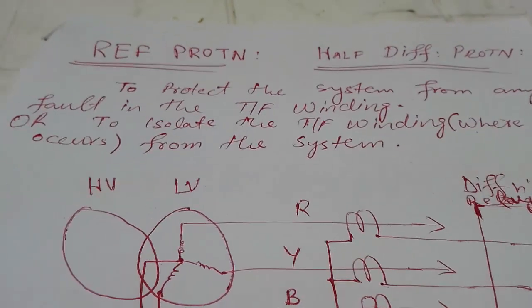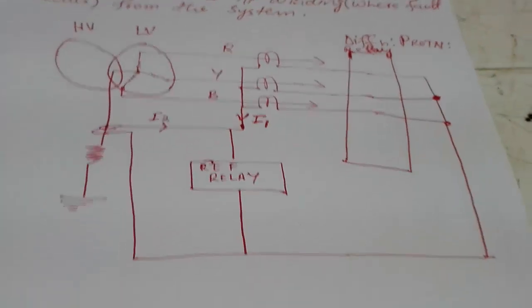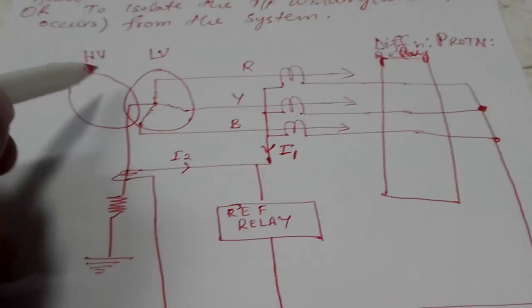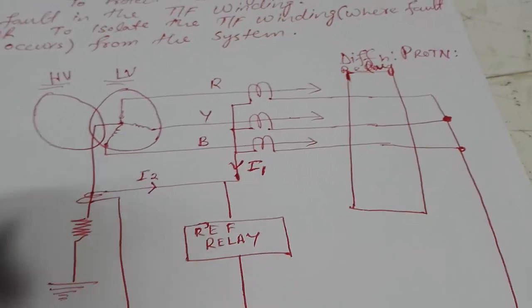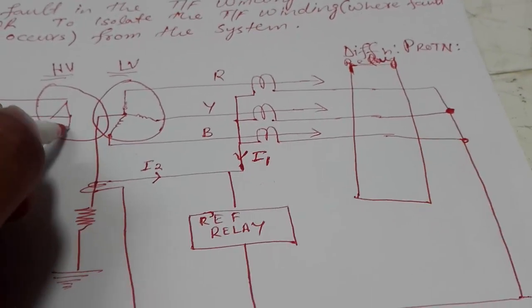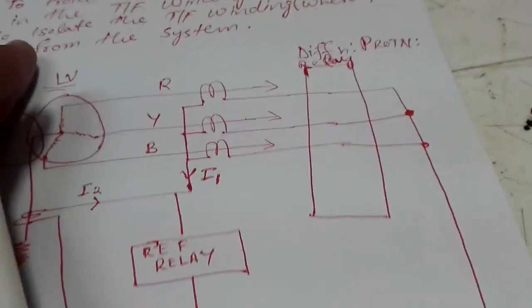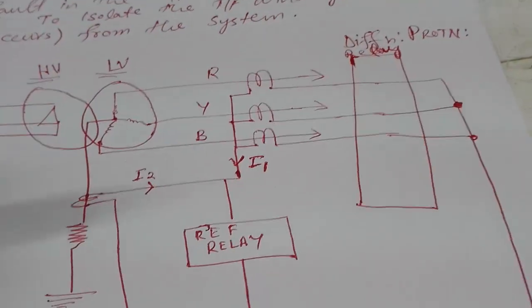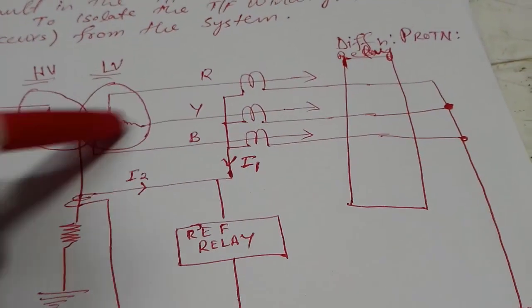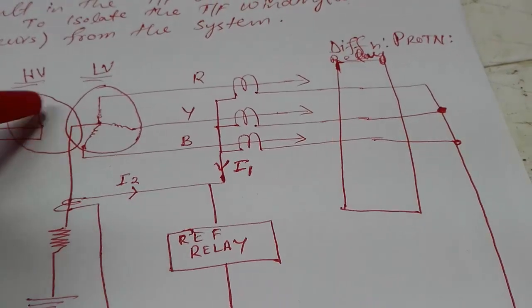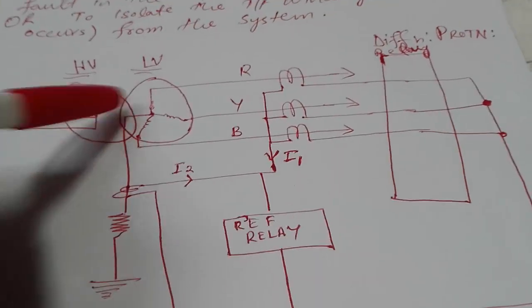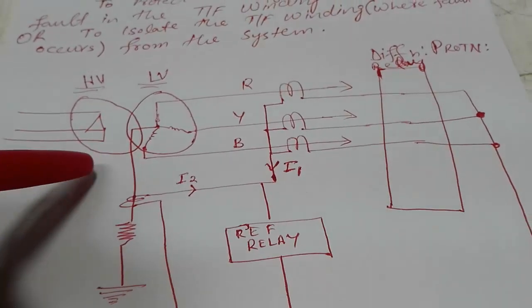The scheme isolates the transformer winding where a fault occurs. For example, this is the HV side of the transformer and this is the LV star side. This section will not be considered in the REF protection. Sometimes it is also called half differential protection, because it only considers the LV side or only the HV winding, depending on which side the scheme is connected to.